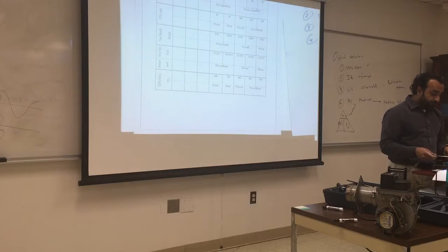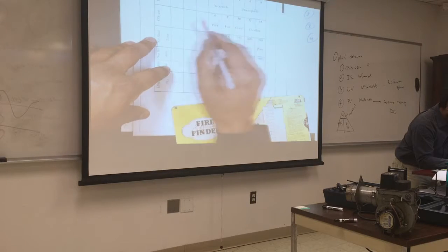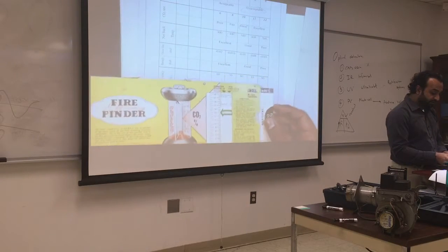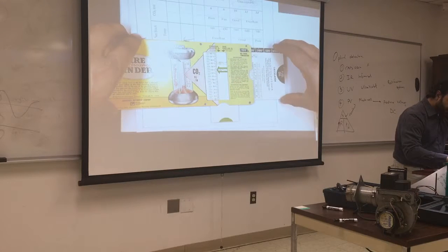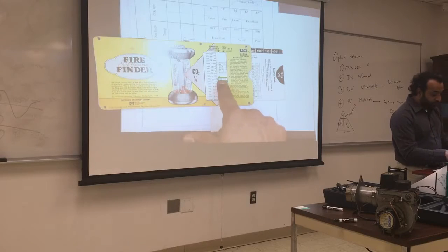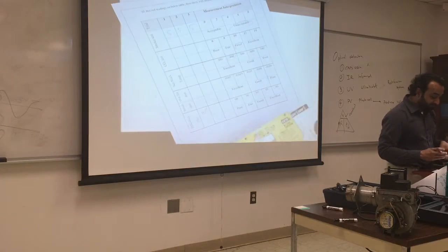That will be your stack temperature and the CO2 measurement. Let's say we got a stack number of 400 and I got CO2 as 10. How do I get the efficiency? I use a slider ruler and I'll put the window here at 400, and I'll slide this down to 10 percent, and that'll give me 82 percent efficiency. I'll do it three times again, 82 percent, which is in the good range. A very new boiler will give you around 90 percent efficiency. An old boiler probably 70 or 75.